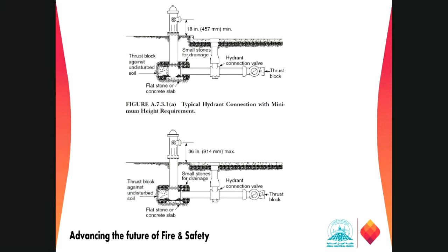They don't care about that, but this is what is required by NFPA 24. So that if there is any maintenance issue in those hydrants, it can simply be closed by the nearby valve. And those valves should be provided with a road box, underground box, so that someone can go and open it, or maybe connected by a PIV, so that someone can operate from above ground.